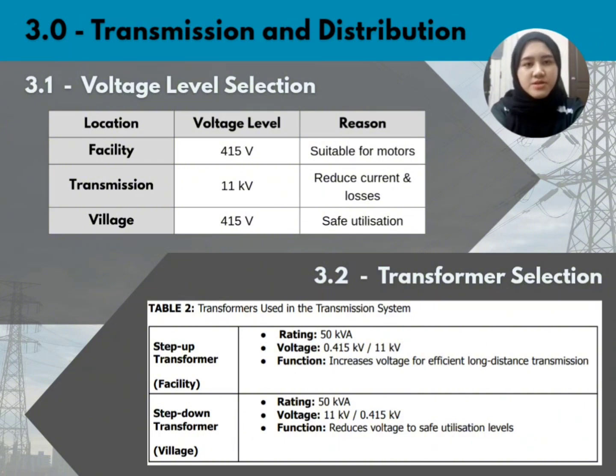For our voltage level selection, to achieve high efficiency, we utilize two different voltage levels. Within the facility, we use a low voltage level of 415 volts, which is ideal for our industrial motors. However, to transmit power to the village, we step this up to 11 kilovolts.